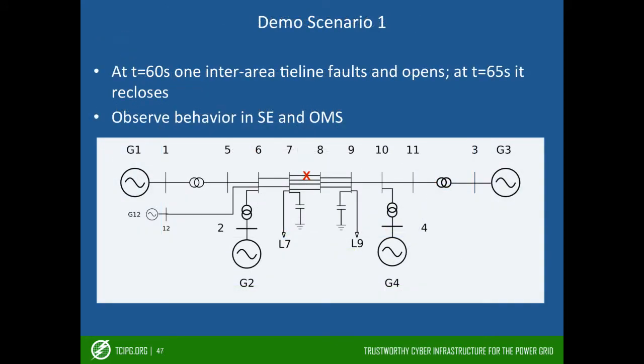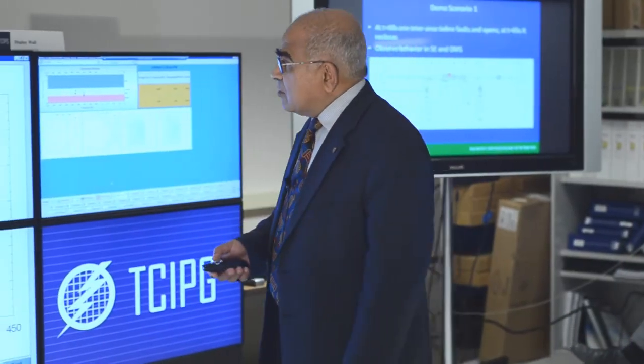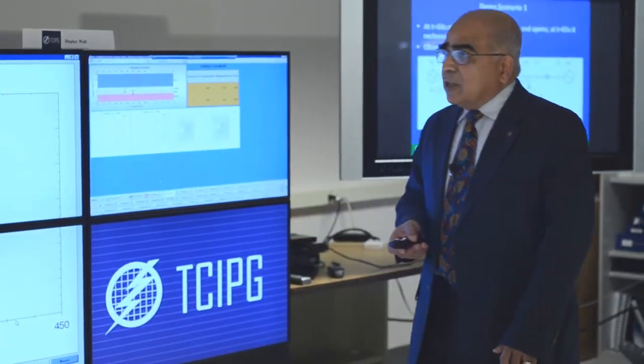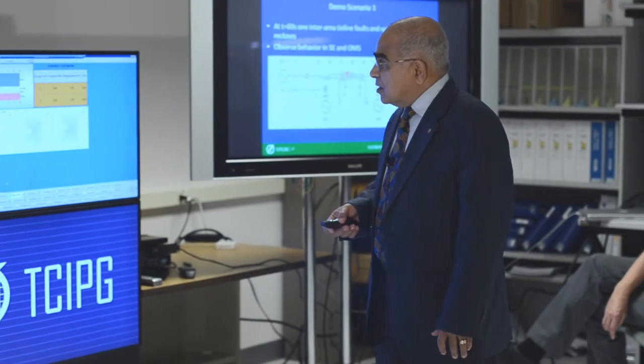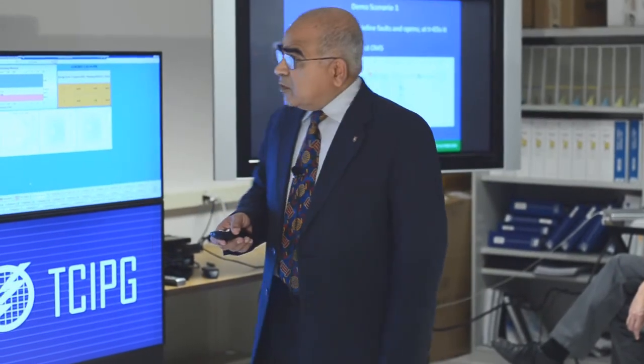Here is what has happened so far: at 60 seconds, a line opened and then closed five seconds later, and everything is now damping out and going back to normal. It caused some oscillations which were picked up by the oscillation monitor, but it was not too much of a problem.